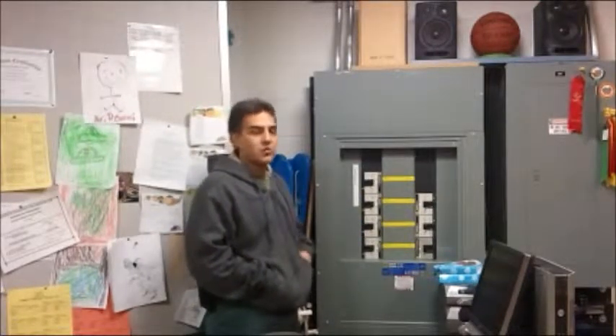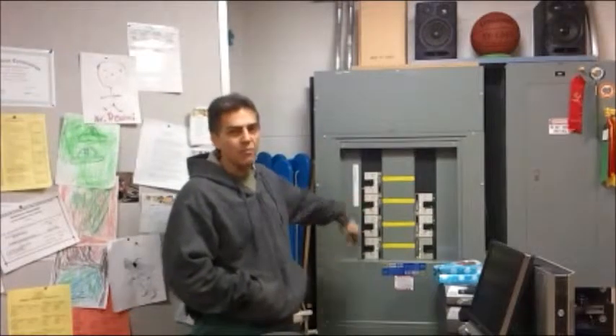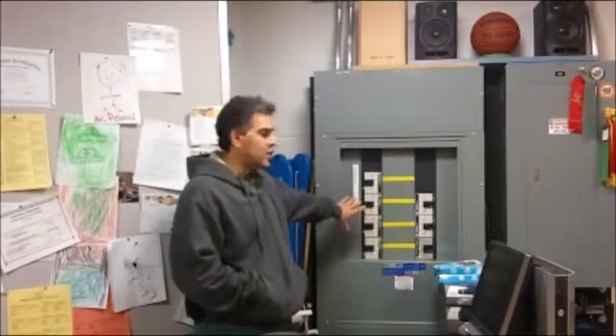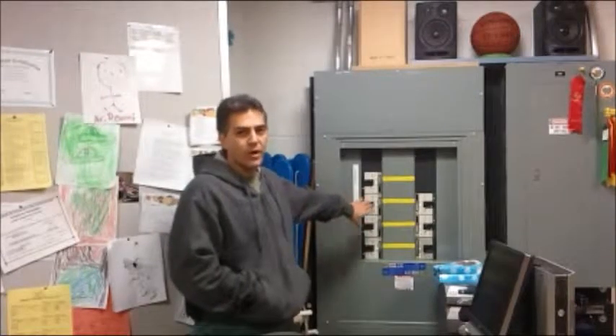So what we're going to do is use the 30 amp breaker, but then I have to breaker down the secondary side of the transformer according to the code, which is going to be cheaper to do that way rather than buy a brand new 25 amp breaker. The secondary is only going to cost about $150 for a disconnect. So I'd rather put the disconnect up rather than change the breaker and spend $400 for a breaker.